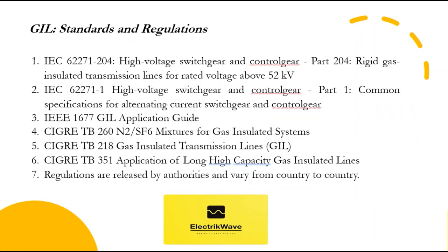The various standards and references followed for GIL include: IEC 62271-204 — High voltage switchgear and controlgear Part 204: Rigid gas insulated transmission lines for rated voltage above 52 kV; IEC 62271-1 — Common specifications for AC switchgear and controlgear; IEEE 1677 — GIL Application Guide; CIGRE TB 260 — N2 and SF6 mixtures for gas insulated systems; CIGRE TB 218 — Gas insulated transmission lines; CIGRE TB 351 — Application of long high capacity gas insulated lines. Regulations are released by authorities and vary from country to country.